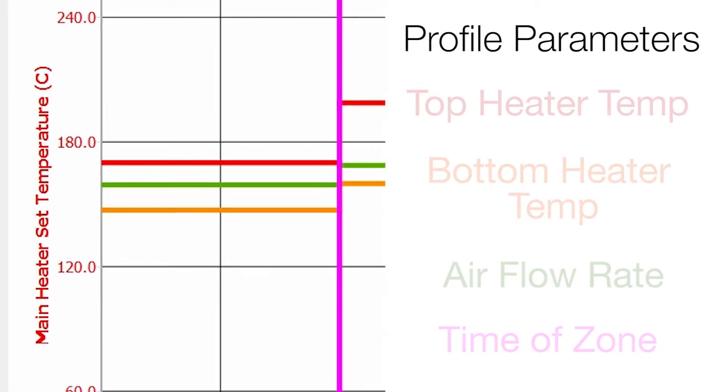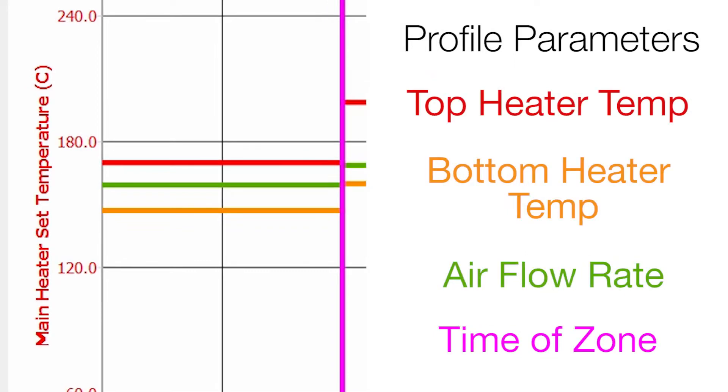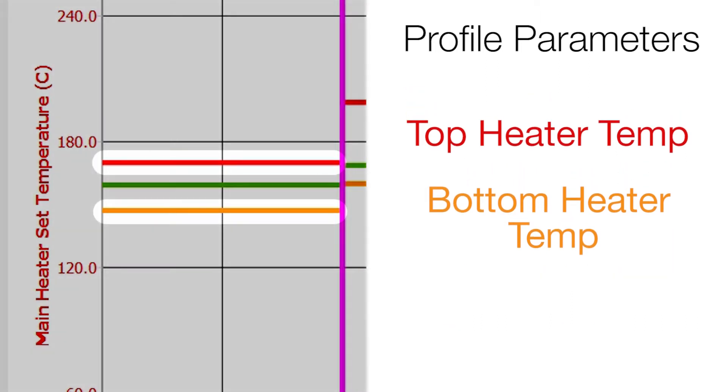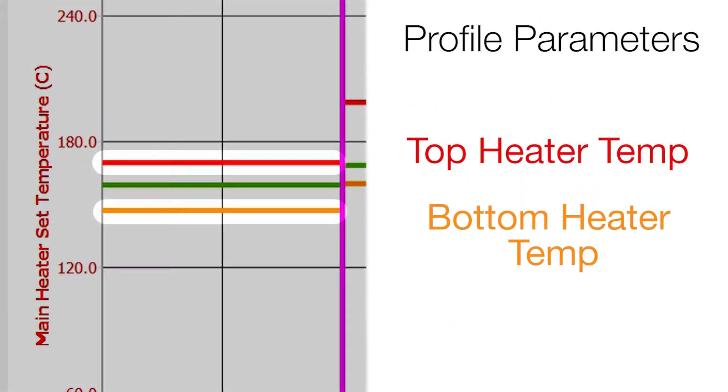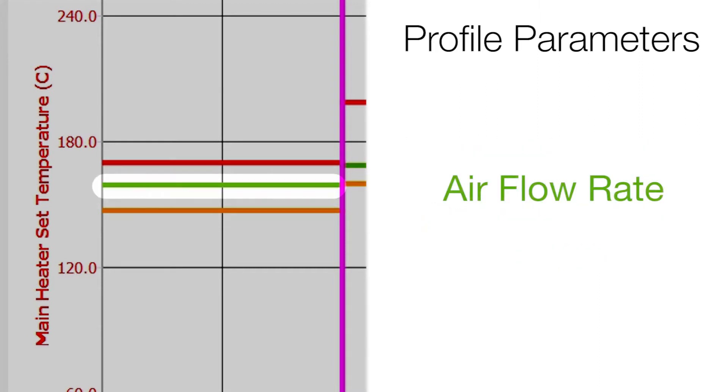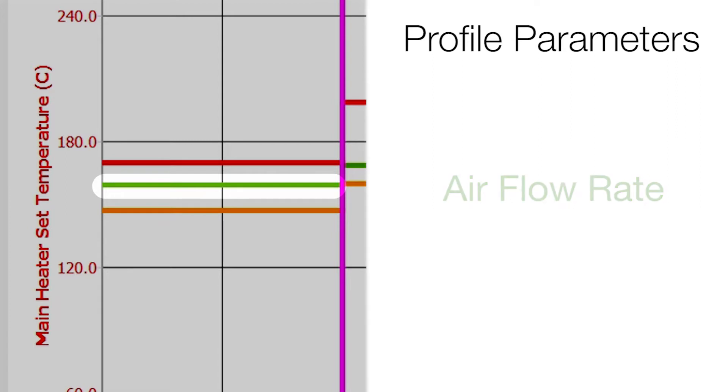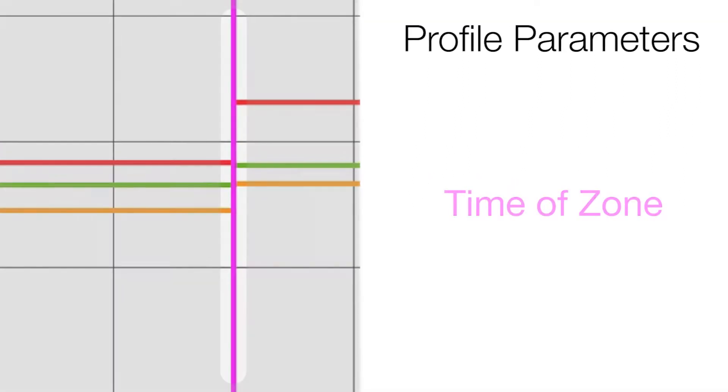Our profile parameters are represented by four different colored lines. The red and orange lines are our top and bottom heater temperatures. The green line represents our airflow rate coming from our top heater. And last, the vertical purple line represents the time for each of our five zones.